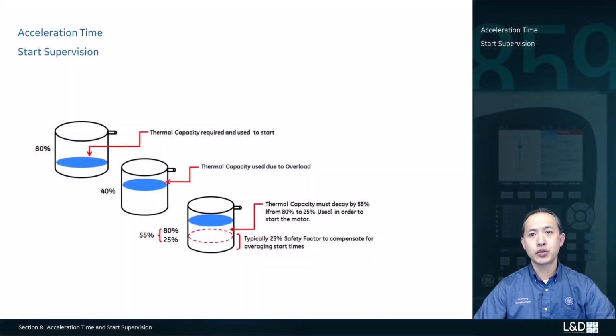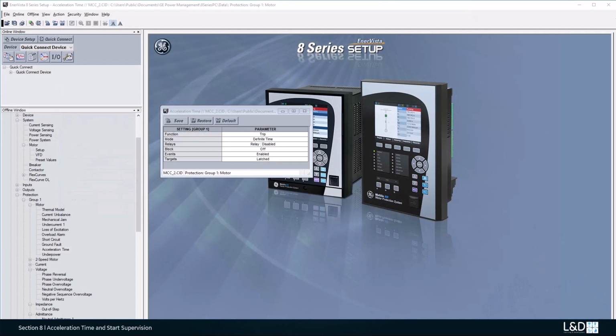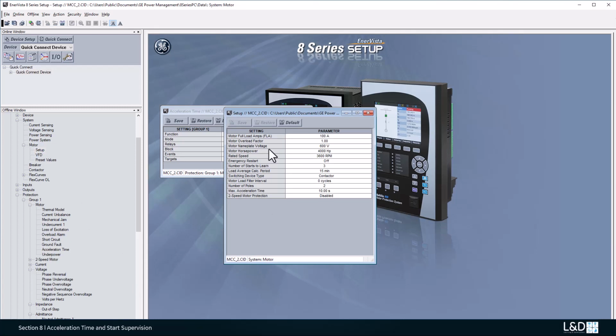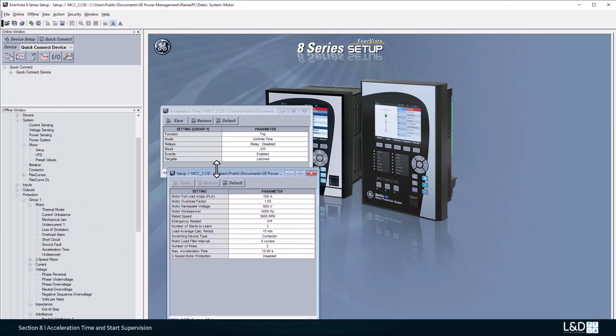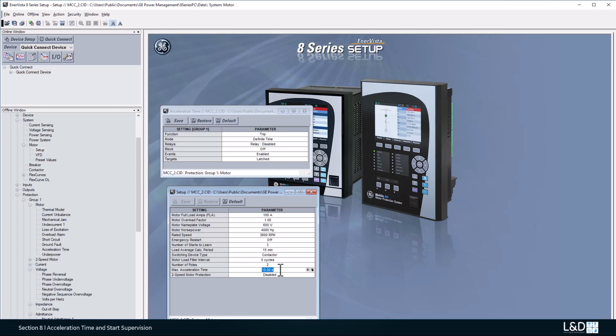In this session, we are going to introduce the acceleration time and the start supervision. All these protections are used for the motor starting or the motor restarting. Acceleration time can detect the stalling during a start and trip the motor before the thermal model operates. This mode can be set to definite time or adaptive, two modes. When set to definite time, then the acceleration time is set under the motor setup acceleration time. Here we set to 10 seconds. The datasheet has the acceleration time of 9 seconds.